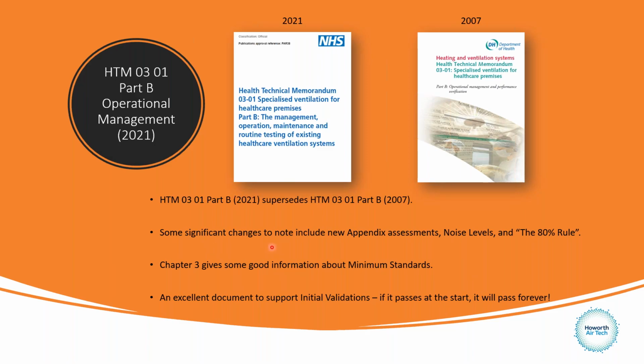There are some significant changes to note, such as new appendices. Noise levels have changed from 75% real world to 80%. Chapter 3 gives good information about minimum standards, and every time I do a validation now I include HTM 03-01 Part B, Chapter 3, Appendix 1 and Appendix 2, because if those criteria are met at validation, they will continue to be met in the future. So we're ticking all the boxes right at the start.